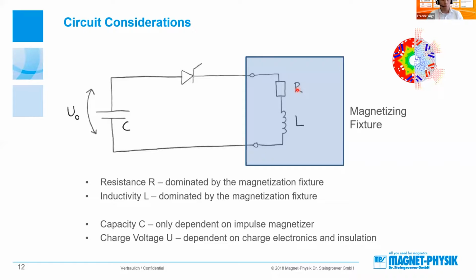And of course, here's also the point where we talk about efficiency, because current can be generated in different ways. The setup is a very simple RLC circuit. So you can see the resistance R and the inductivity L dominated by the magnetization fixture. And you can see the capacity from the magnetizer and the charge voltage of the capacitor. The charge voltage depends on the charge electronics, but of course also on what kind of insulation we have for all the windings in here and for the rest of the magnetizer. In our case, we use 3000 volts, which we feel is a good level of voltage, not too high, not too low, to give us a good magnetizer sizing.